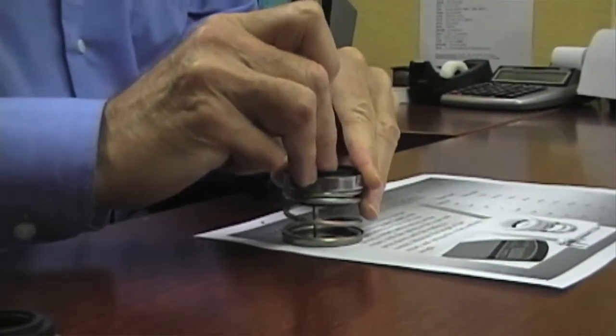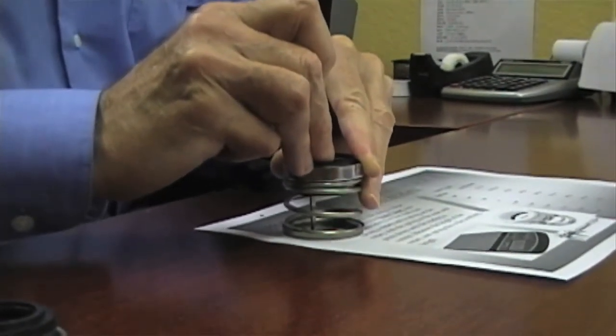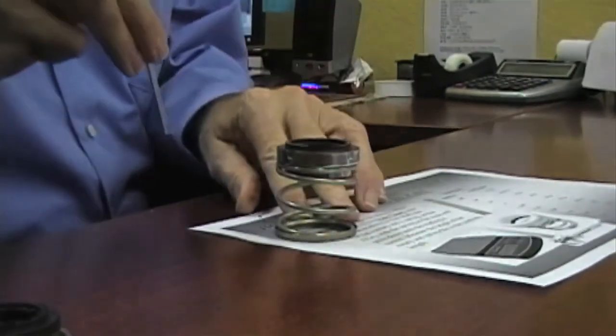Do the same thing. In this case, it's pretty obvious — the longer working length has no squeeze on the seal. This here is a shorter working length seal.